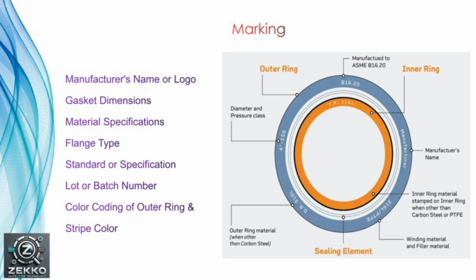Basically, the manufacturer's name or logo identifies the maker of the gasket. Material of the winding indicates the type of metal used in the winding, like SS, Monel, Inconel, and filler material like graphite, PTFE or mica. Pressure ratings have various classes like 150, 300 or 600. This is the pressure class the gasket is designed to handle. Size or dimension, like inner diameter, outer diameter, and thickness, are commonly expressed as ID, OD and thickness on the gasket. Standard of compliance indicates that the gasket complies with the relevant standard like ASME B16.20 or API 601.